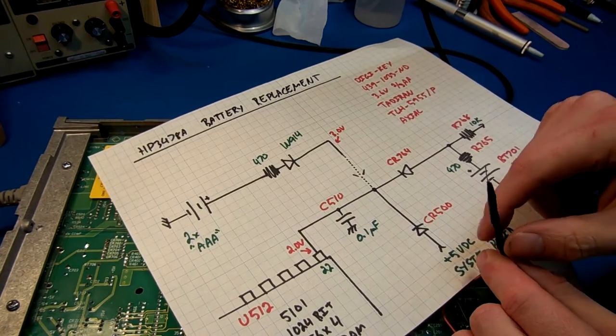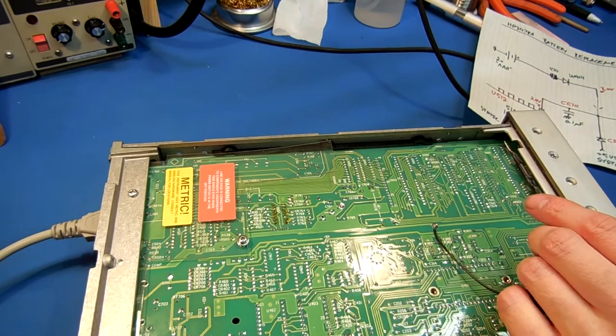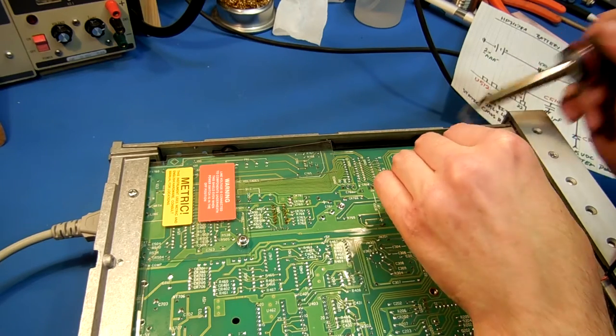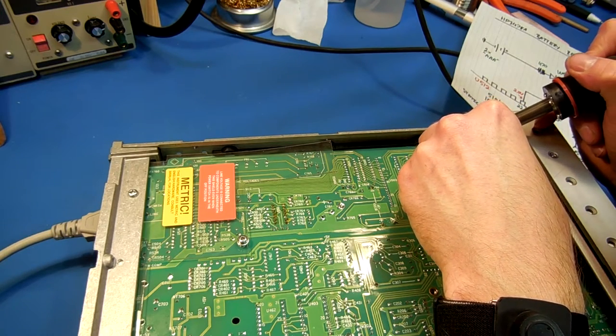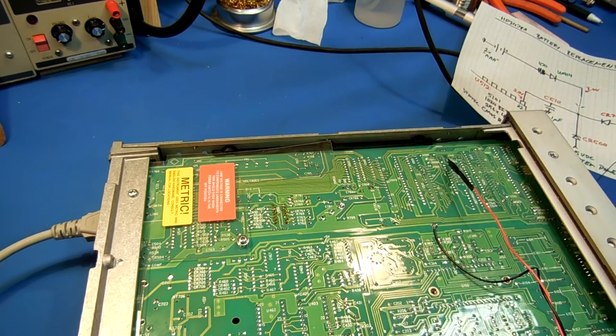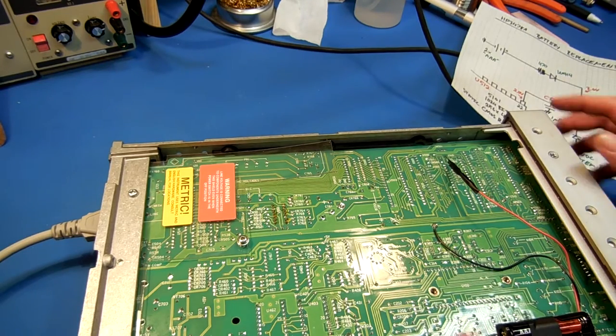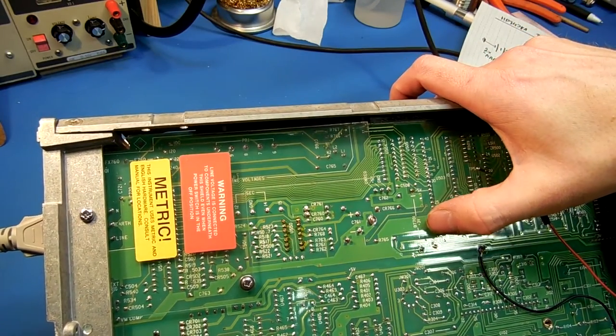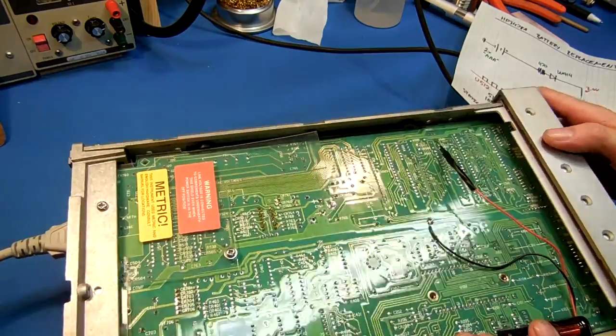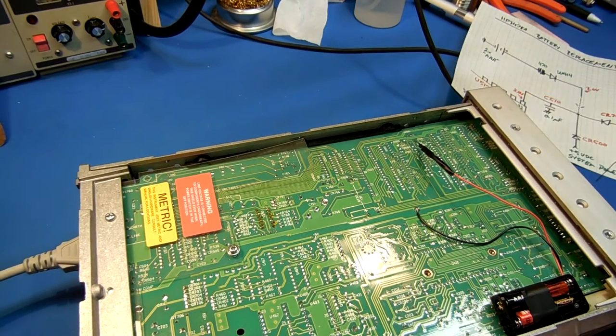I just put electrical tape on there just to keep it from shorting out if it were to touch. This is going to go to the left pad there on C510. Okay. Now, here's the solder pads for the original battery. It's labeled BT701. This is the plus. This is the minus. We have our backup installed in parallel. And, double-checking the front panel looks okay. No error messages.